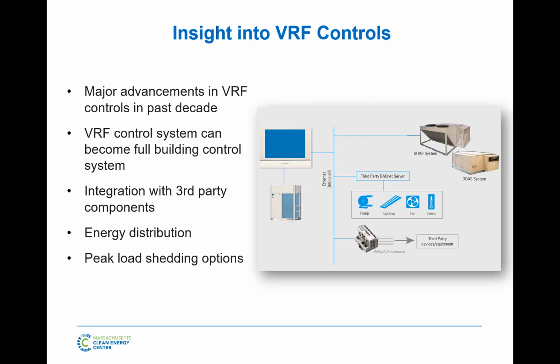So now the idea is these units have all sorts of ways of integrating third-party equipment. They can be done through analog connections, digital connections, or even through BACnet. So what that means is this system can talk to the DOAS units. Of course, if you're using a VRF manufacturer's DOAS, it talks the same language and goes right in. But if it's a third-party DOAS unit, we can use all sorts of different connectors to talk to those. So on your manufacturer A's central controller, you see all the VRF units, and then you're going to see manufacturer E's rooftop unit, manufacturer F's exhaust fan, if ever you decided to mix and match or you're going into an older building. That's a big part of the story now.